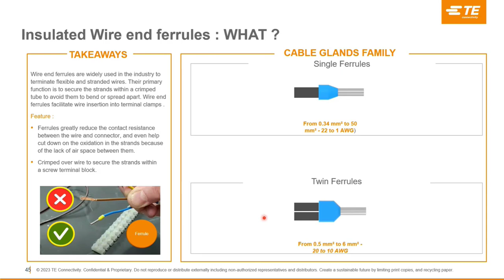Next question: how does the ferrule get selected for any application? We need to check the cable size, then whether it is an insulated or non-insulated ferrule the customer is looking for. As you can see, the left side is a non-insulated ferrule and the right side is an insulated ferrule. Then we need to check with the customer what ferrule pin length they are looking for, which is very important, then whether it's for single wire or double wire.